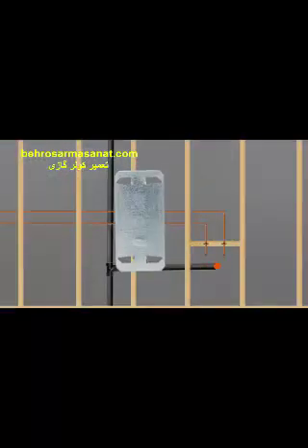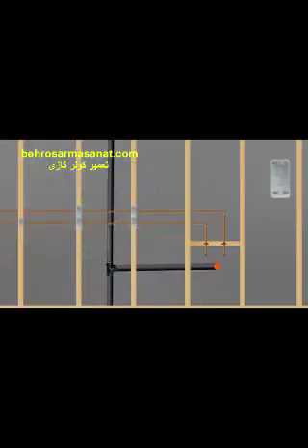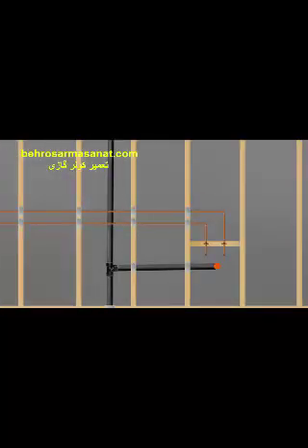The second reason why you'd fail an inspection would be that there are no drill plates or protection plates. These protection plates are specifically made for this, so always install them before calling your inspector.